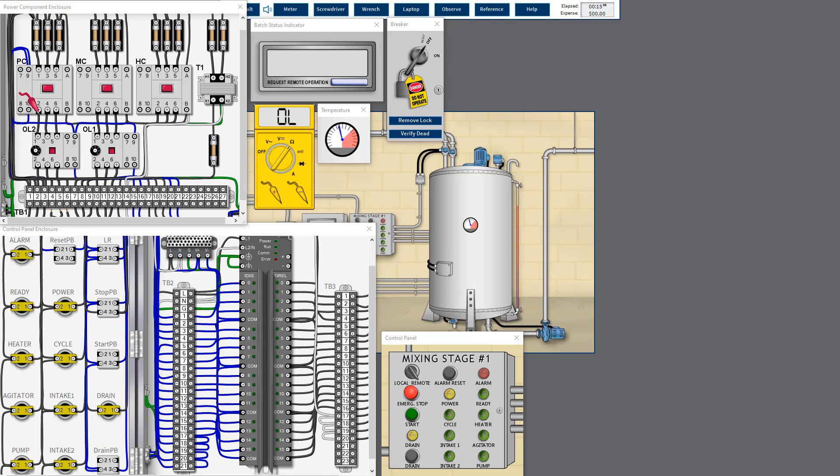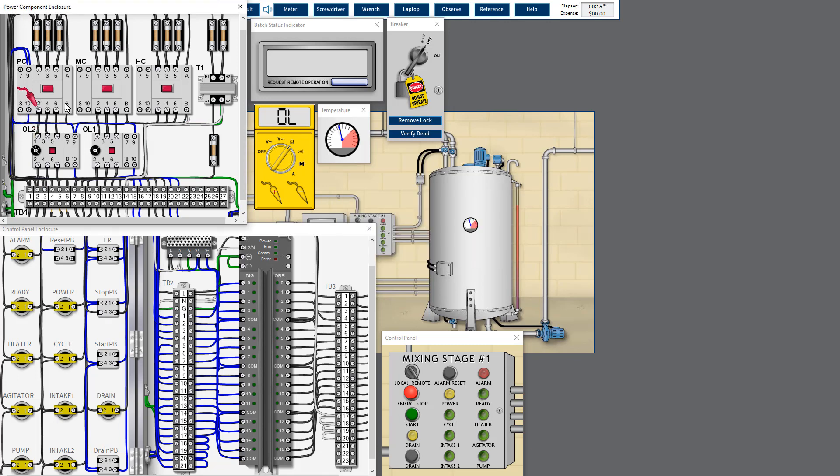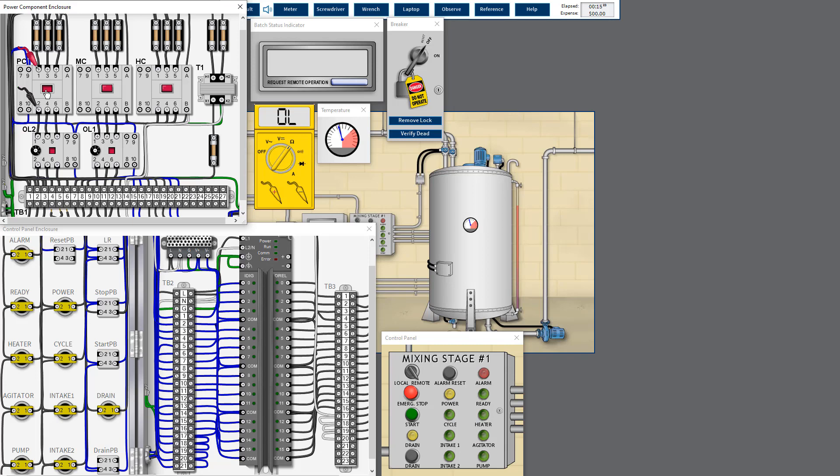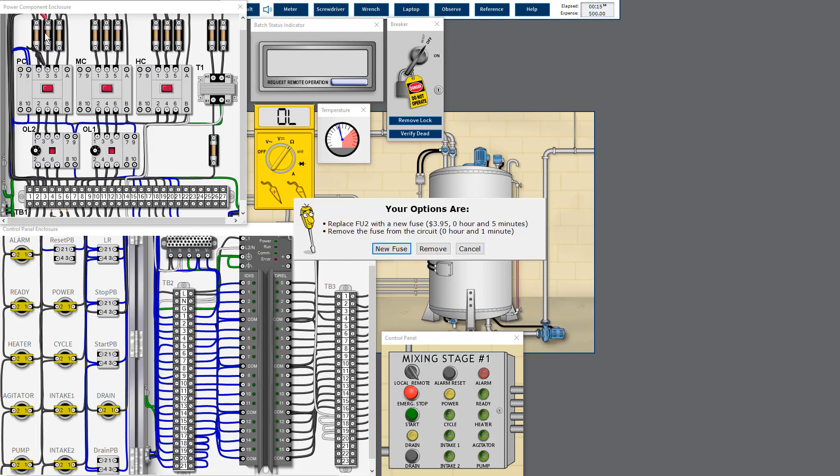So we can measure further on. Still the overload, okay, then we measure here to confirm there is no open circuit on the fuse. Now we check the resistance across the contactor. Yeah, contactor having internally open circuit, okay, so the contactor need to change. How about this line? Oh, there's open circuit, so we have double confirm, so the fuse is blown, okay. Then how about this one, the third phase? Okay, looks okay. Okay, the fuse is blown for the second phase, okay, so we have to change the fuse here.